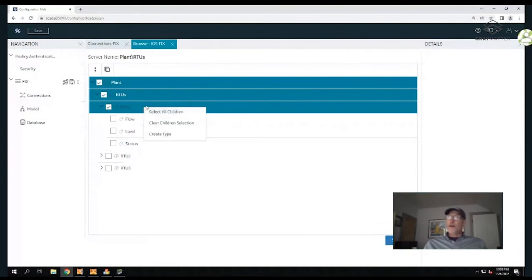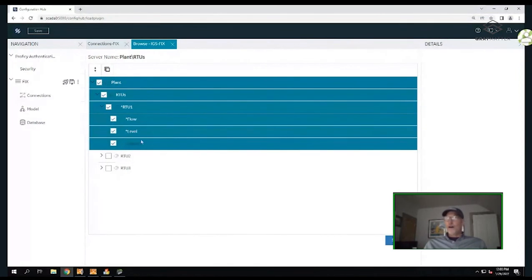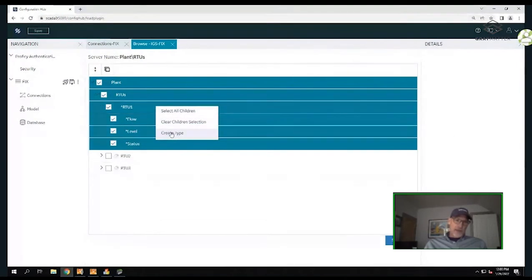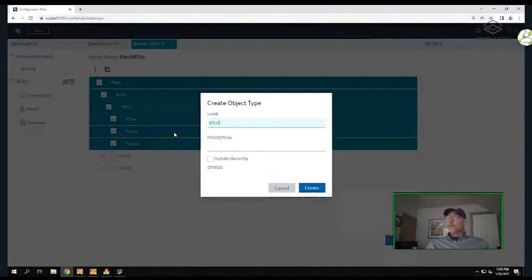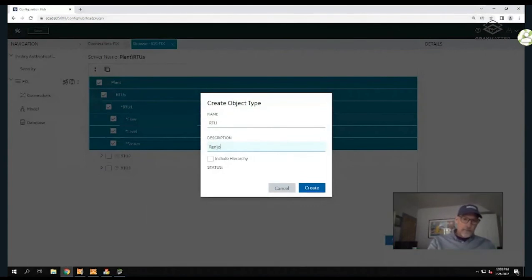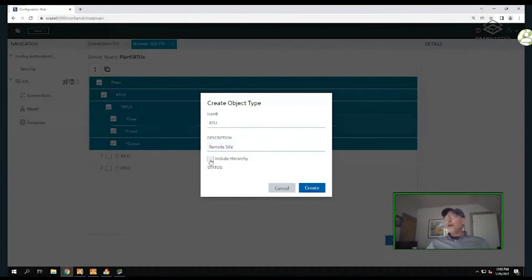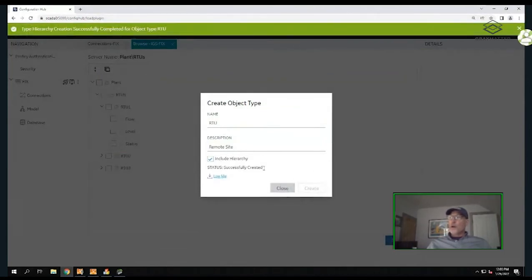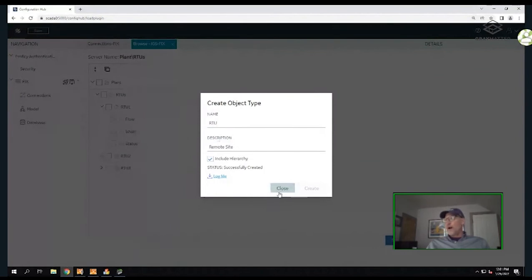I've selected RTU1, and by right-clicking, if you have a bunch of process variables under that, you can say Select Children, and it will select the process variables underneath. Instead of staging individual tags, I'm going to right-click and create a type - an asset type used for my model. I'll click Create Type, call it RTU, keep the same hierarchy, and create it. If there are errors, there's a log file generated with a hyperlink to see what's going on.